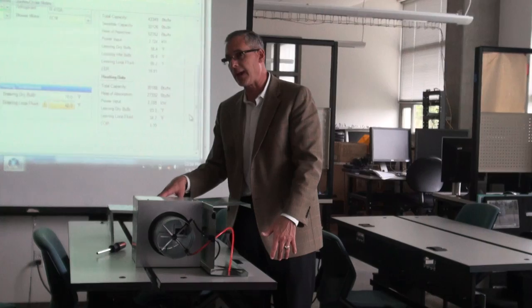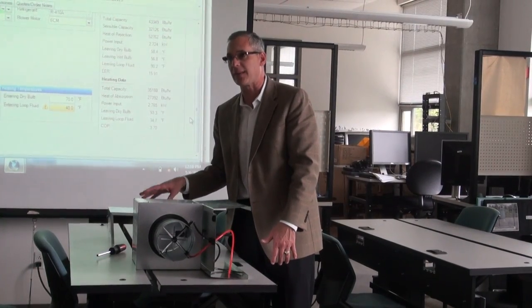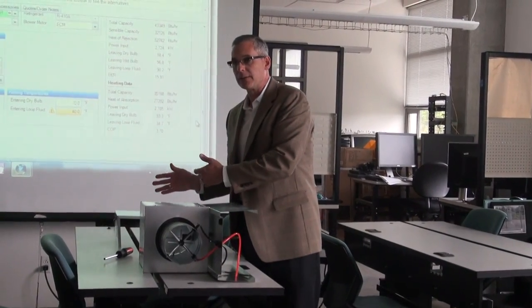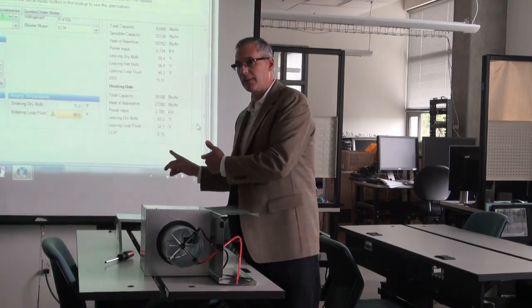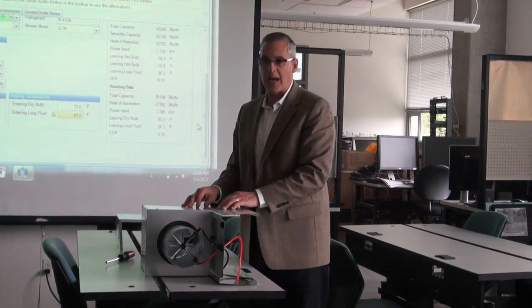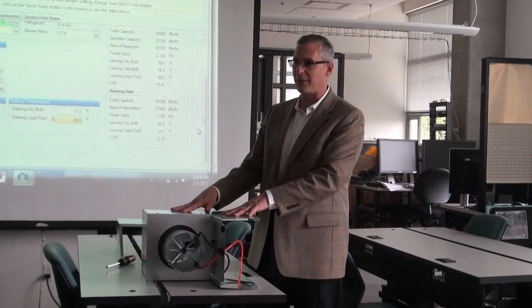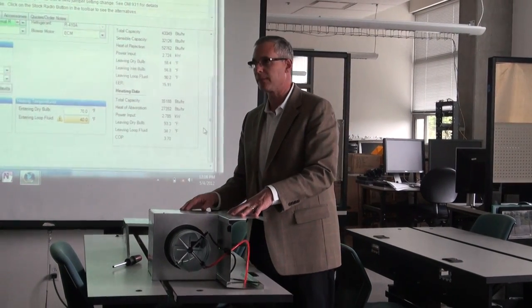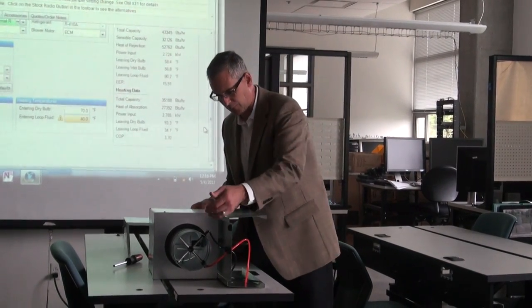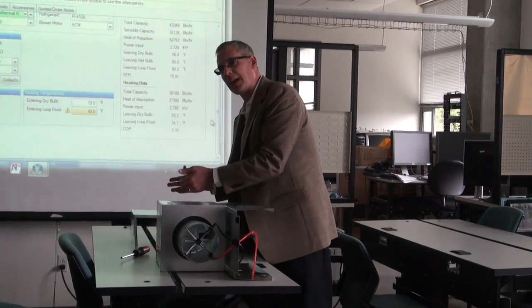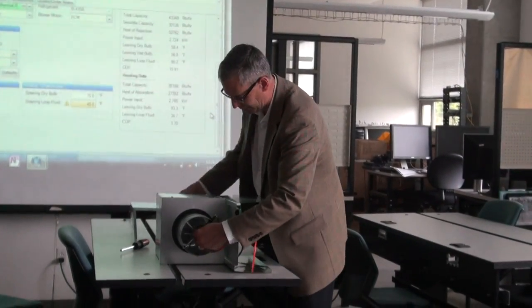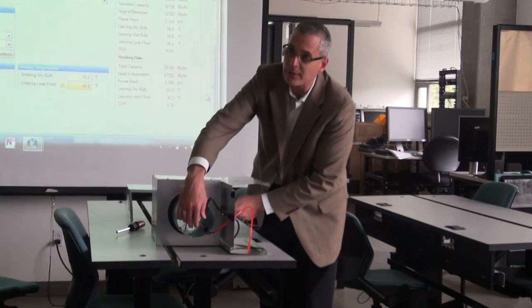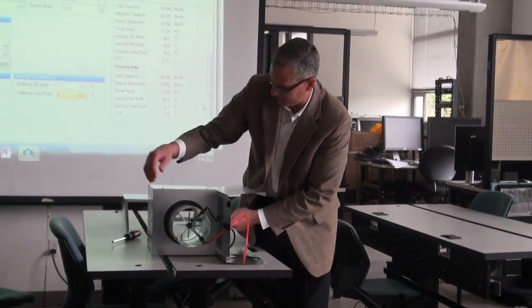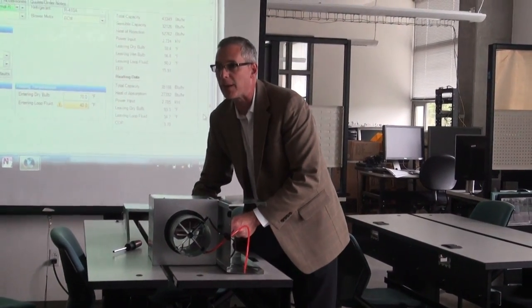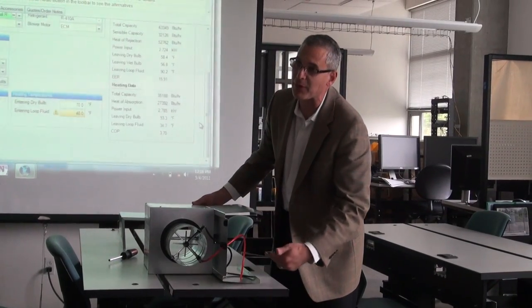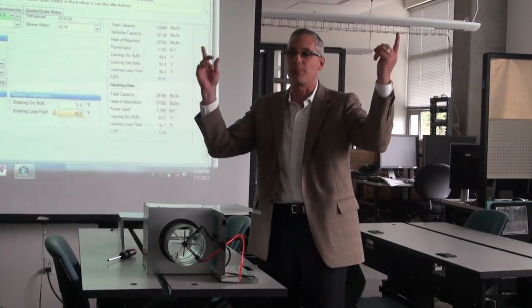In a series fan-powered box, it's always blowing the same amount of air. It's constant downstream. So if you had a size 0811 with 1,000 CFM, or, well, 800 CFM was more in line with that, you would always have 800 going out, even though this valve may be turning down to only allow 300 CFM in. That means the other 500 is coming through that other opening in the return plenum.